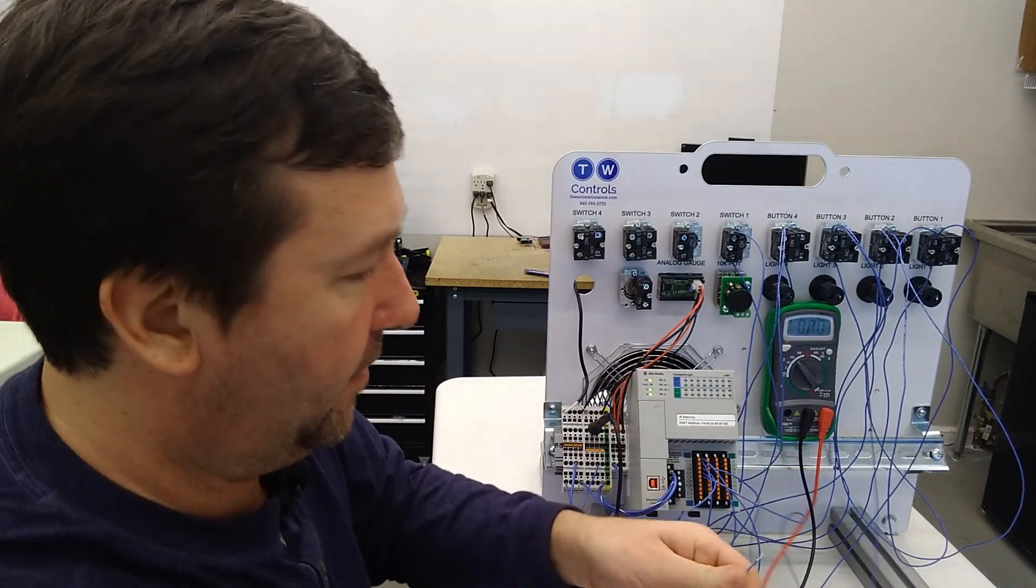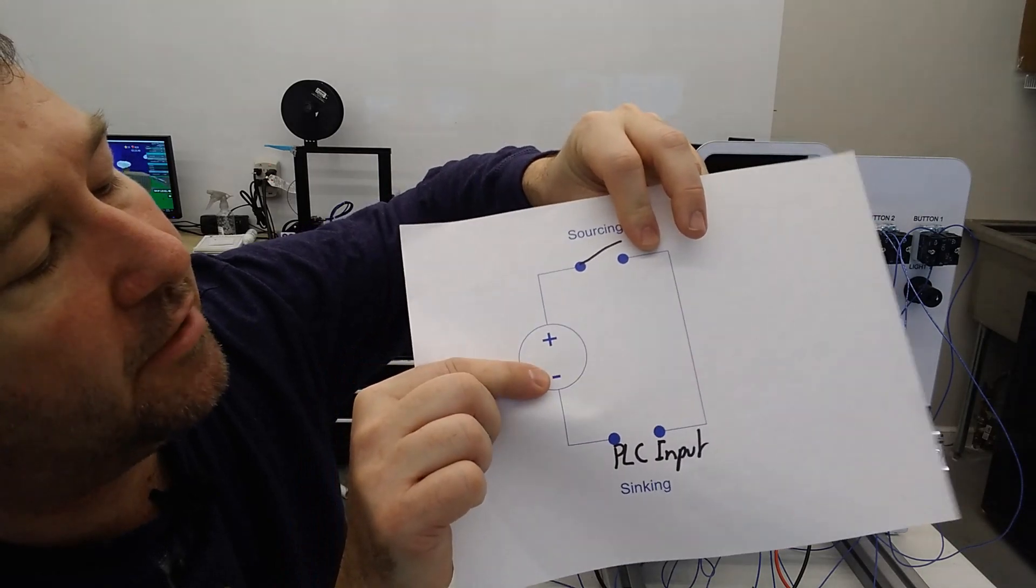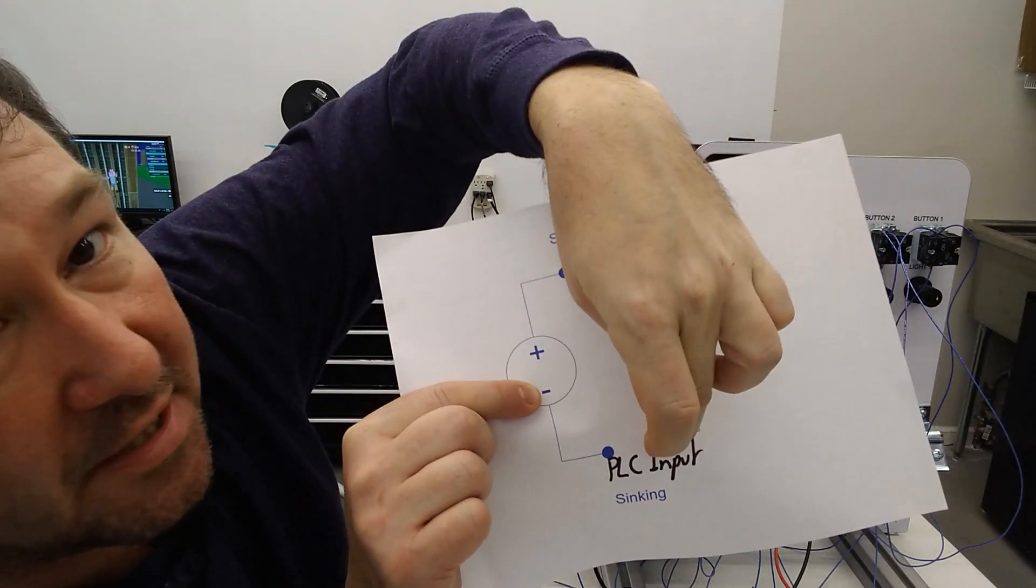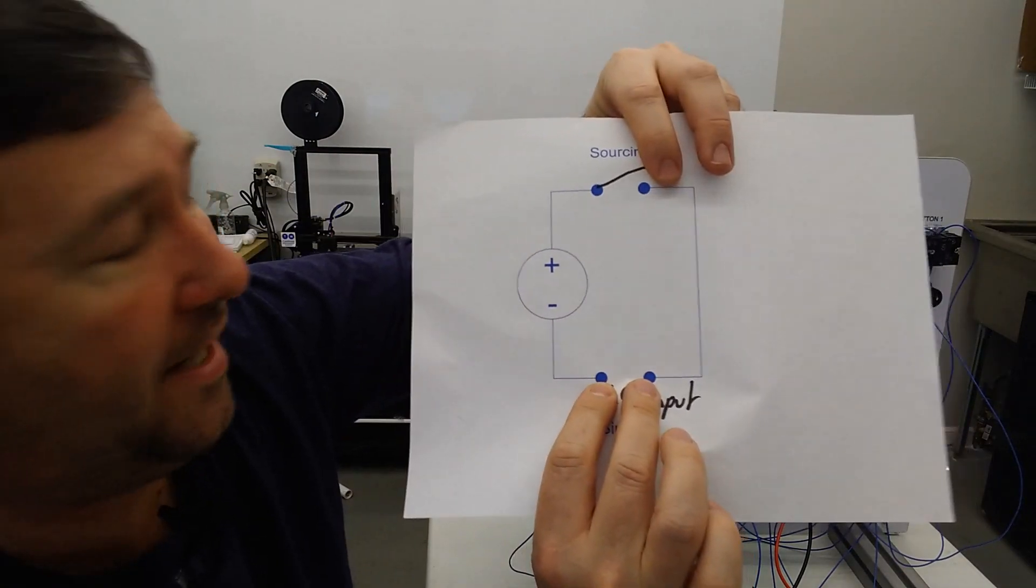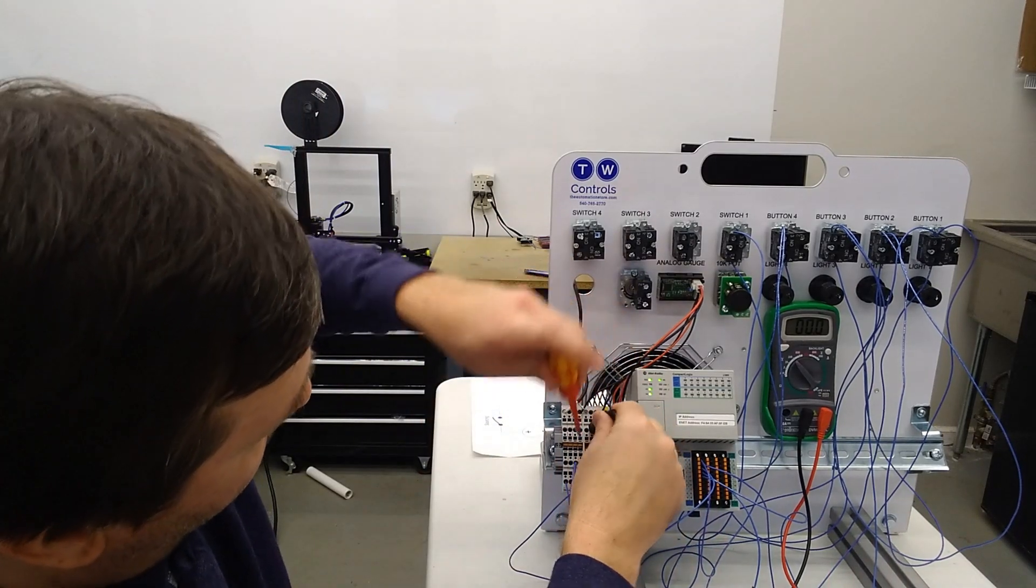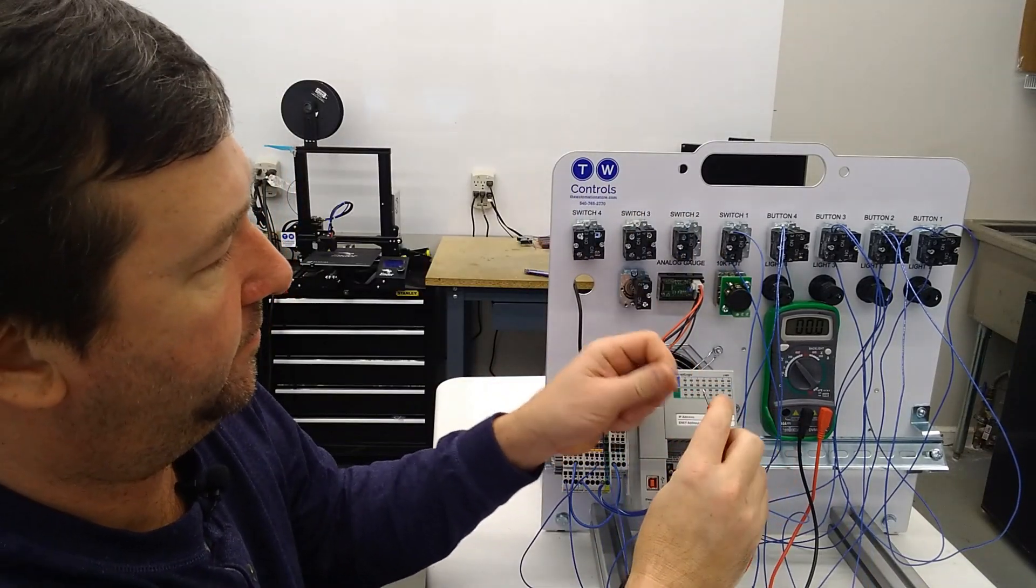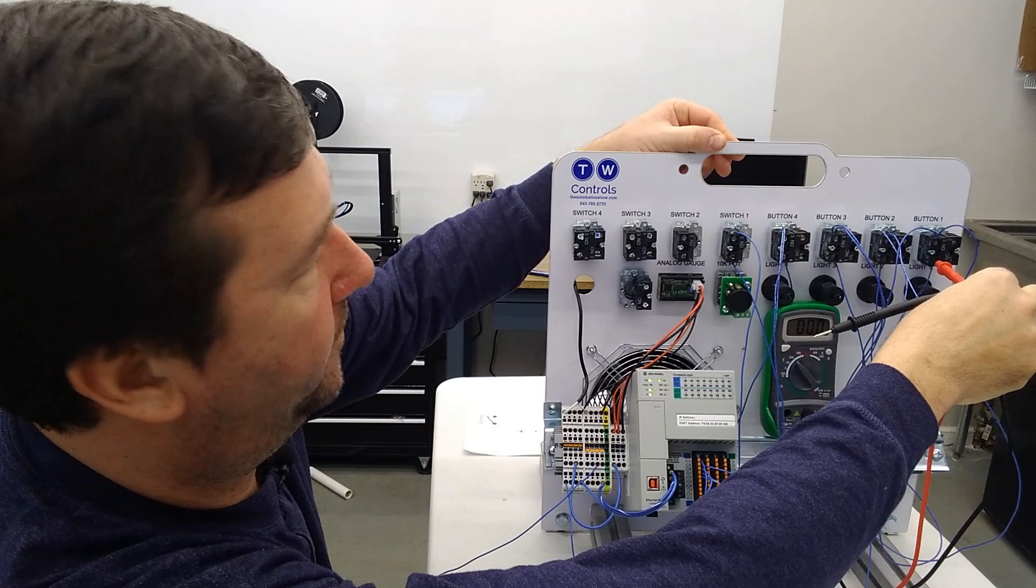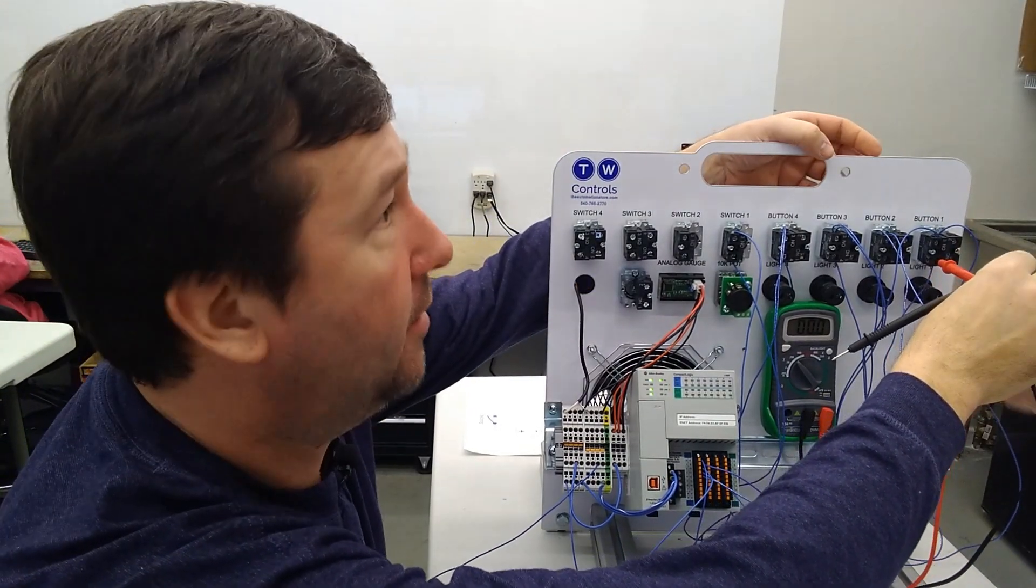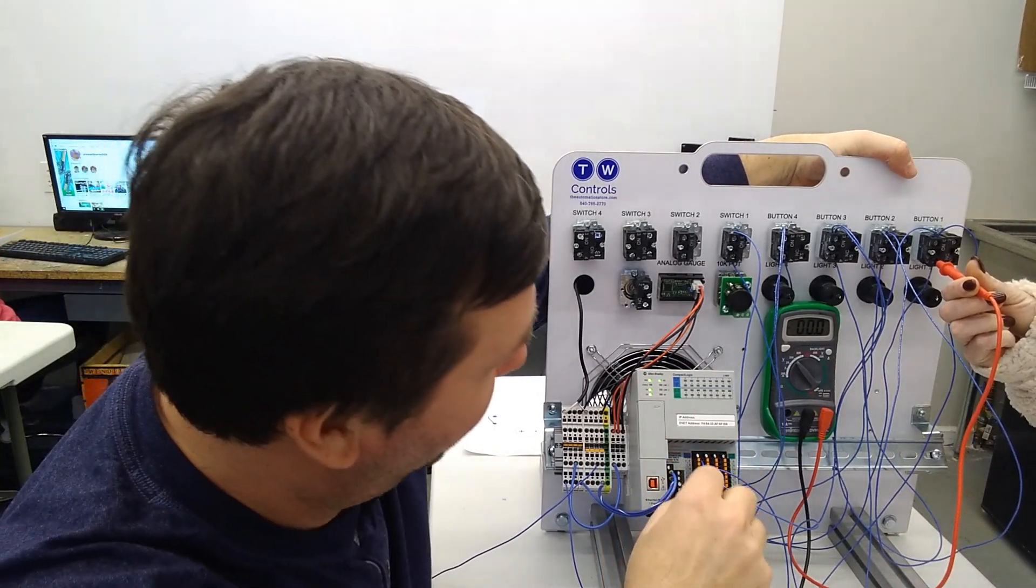And even if we take a wire and we slide it right down beside of that terminal, because it's a little tight to get your voltmeter on, you press the button and we have 24 volt at our terminal. The issue is I'm taking my voltmeter and testing right here at this minus terminal. And I'm testing to here, to here, and to here. I'm not actually testing across this PLC input. That's where you really have to check at. So since it's the FP minus terminal, if I remove my voltmeter from the minus and I connect it over here to the FP minus terminal. Can you be my assistant for a second? Can you come over here and hold that on button one?